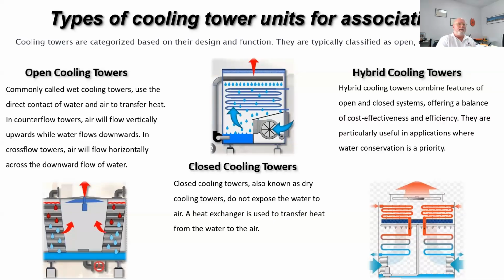In addition to how the water is evaporated, there are different types of cooling towers based on the material they're made of. Here in South Florida, there's a case to be made for using fiberglass towers because of corrosion. On the other hand, using stainless steel or traditional towers is not uncommon and is still an appropriate response. But there are a lot of things to discuss with your engineer, because there are drawbacks to both - obviously steel systems tend to rust more.